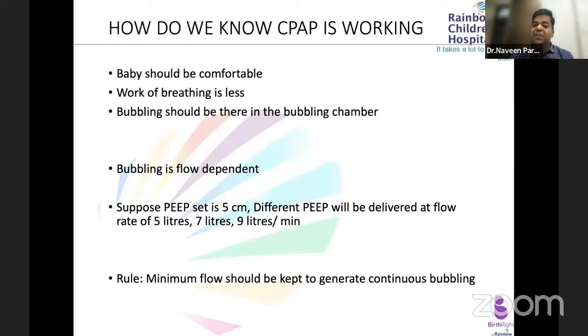And always remember that when we are putting the baby on bubble CPAP, the bubbling should be there in the bubbling chamber. If the bubble is not there in the bubble chamber, that means the positive pressure is not there. Either there is a leak around the interface, or there is a leak somewhere in the circuit, or the flow is insufficient. So always remember that bubbling is flow dependent.